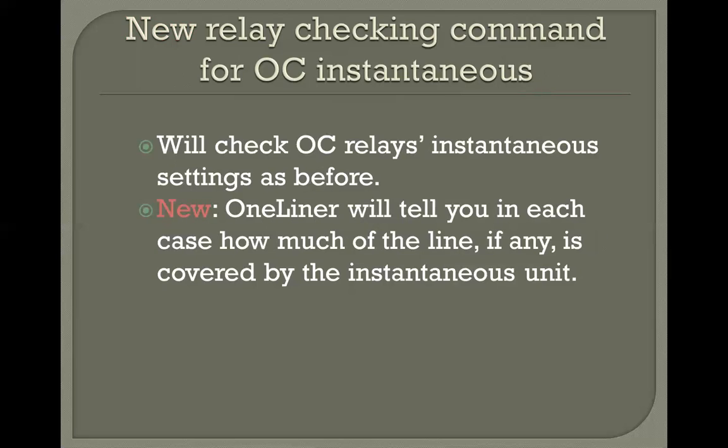But what is new about the new command is not only that we tell you whether it does not trip on the remote bus fault and trips on a close-in fault and so on. The new command will actually tell you exactly how much of the line is covered by the instantaneous unit. For example, it would tell you it covers all the way from in front of the relay to 30% of the line.